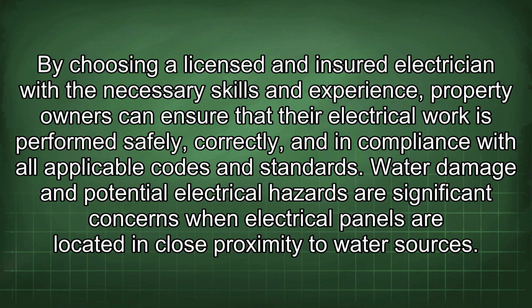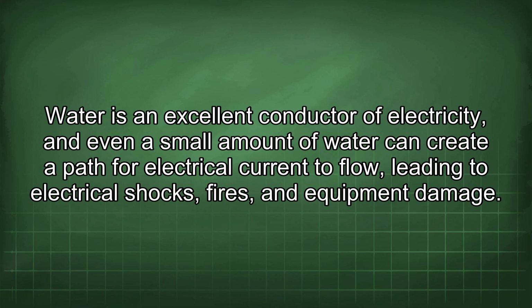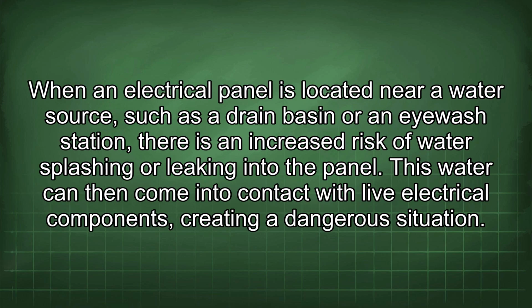Water damage and potential electrical hazards are significant concerns when electrical panels are located in close proximity to water sources. Water is an excellent conductor of electricity, and even a small amount can create a path for electrical current to flow, leading to shocks, fires, and equipment damage. When an electrical panel is located near a water source, such as a drain basin or an eyewash station, there is an increased risk of water splashing or leaking into the panel, which can then contact live electrical components, creating a dangerous situation.